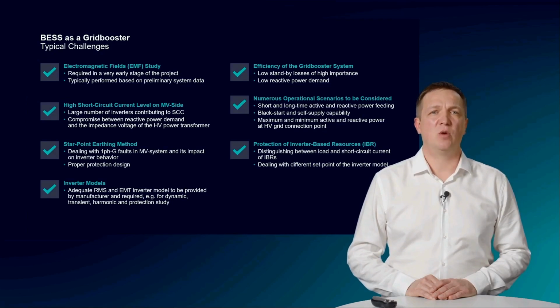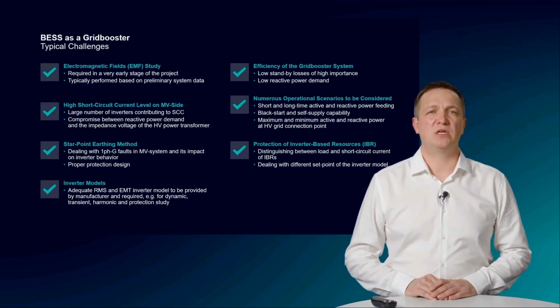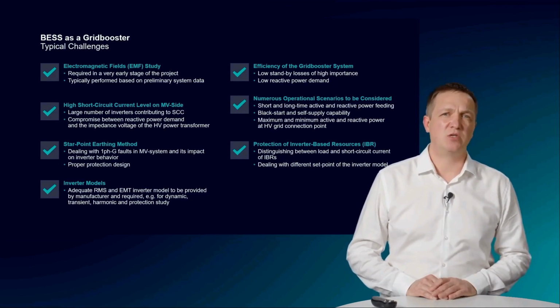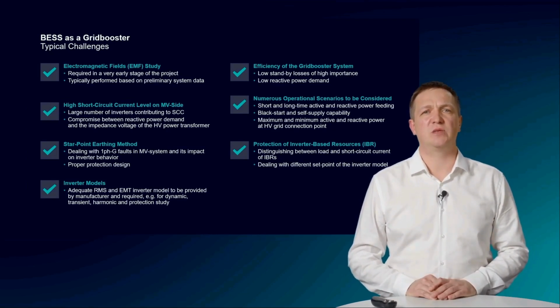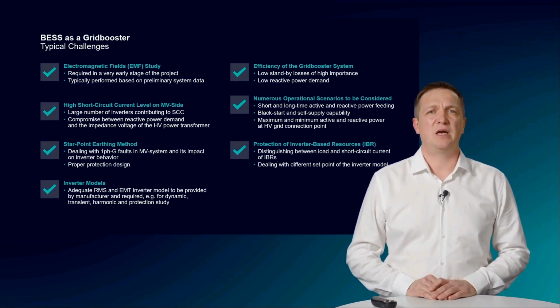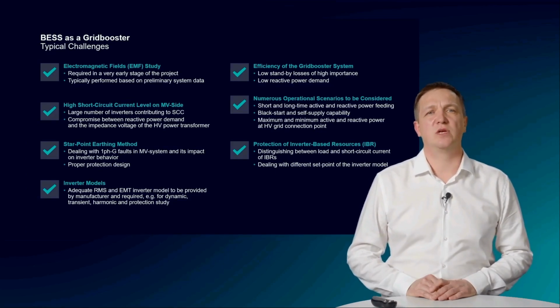One of the major requirements when designing a grid booster is low standby losses and low reactive power consumption. As the grid booster is operating on demand, its standby losses shall be kept as low as possible to fulfill economic and environmental requirements. The losses are checked, calculated, and measured at different stages of the project, starting at the design stage using preliminary values provided by the manufacturer, then at the engineering stage when the loss values are verified during the factory acceptance tests by the manufacturer, and last but not least, the total losses are measured on site with all components connected together.